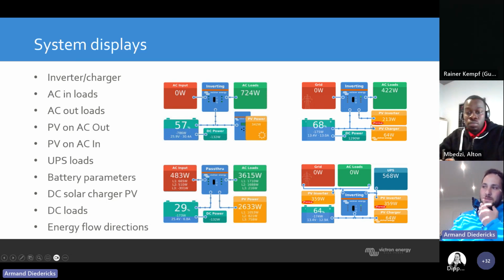This is the AC coupled system. Gideon, your question here, AC coupled system with a PV inverter connected to the output of the inverter. So yeah, it's an AC coupled with a grid-tie system connected to the output. You can see the primary function of the PV inverter is to take over the load as first priority. PV will charge the battery and then take over the load. And then the DC load. On the left corner, it's the basic function PV inverter. This is the old PV inverters. This is how the new PV inverter is displayed. PV inverter load, AC input, and then the battery side. And then on the right corner, if you've got a grid-tie inverter connected to the input.